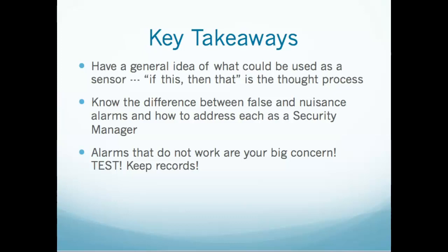Know the difference between false and nuisance alarms. How do you address each as a security manager? You know that false alarms are a system malfunction, and therefore you need a technician to work on that to fix that malfunction. A nuisance alarm is normally a failure of a person to notify you or to use the system properly, and that is normally a training thing. But know the difference between false and nuisance and use that terminology. It's a false alarm or it's a nuisance alarm. Make sure your guards, when you get into a security management position, if you have guards, use that same terminology so that you know whether you need to send a technician or whether you need to go retrain someone.